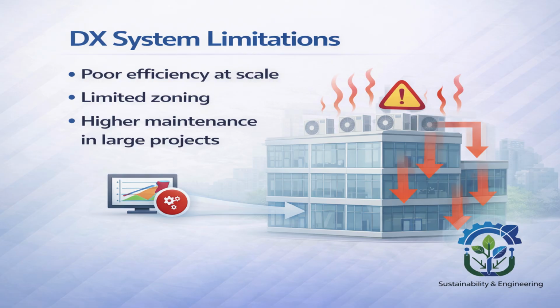The third limitation for DX is higher maintenance in large projects. In large buildings, DX means many outdoor units, many compressors, many refrigerant circuits, and many potential failure points. Maintenance becomes repetitive, costly, and difficult to manage. A single failure may not shut down the entire building, but frequent failures create long-term operational problems.